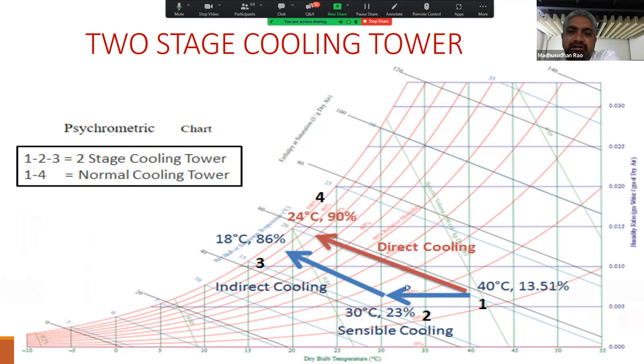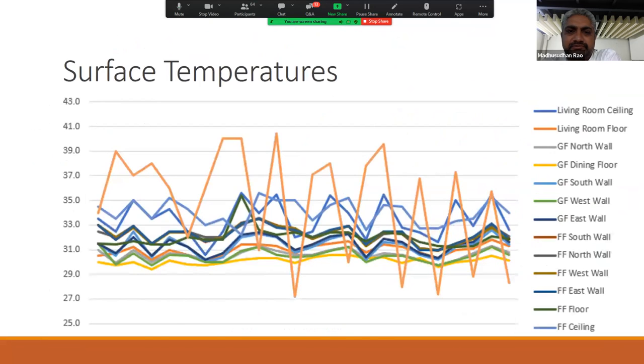A two-stage cooling tower, just like an IDEC, which allows indirect-direct evaporative cooling, lets you get lower temperatures. You apply the same principle to the cooling tower and get lower temperature water, which will enhance your output.